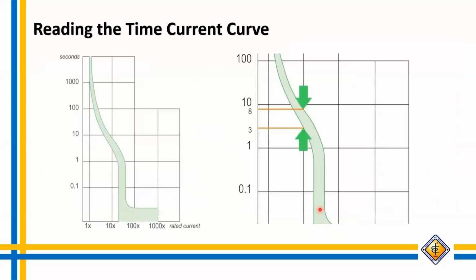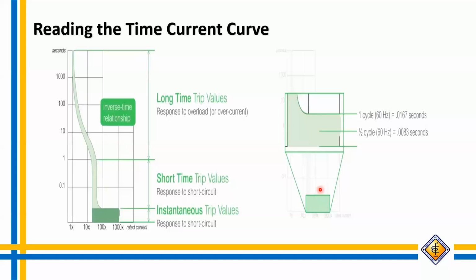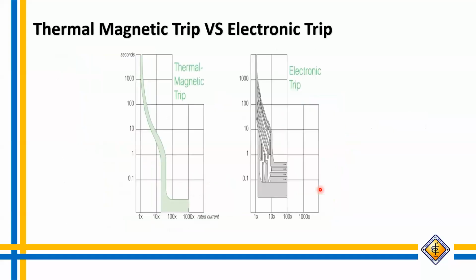So for this one, it's only showing the maximum and minimum tripping capabilities of the circuit breaker. For example, this one has a 3 seconds minimum tripping capability and the maximum is 8. So what it shows there is the maximum, minimum, or the threshold or limit of a particular circuit breaker. Okay, that's it. So for thermal magnetic, it's fixed.